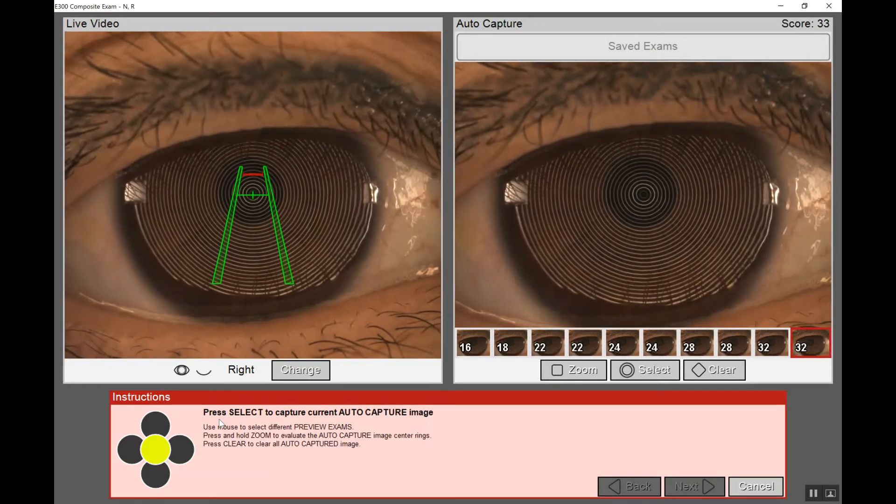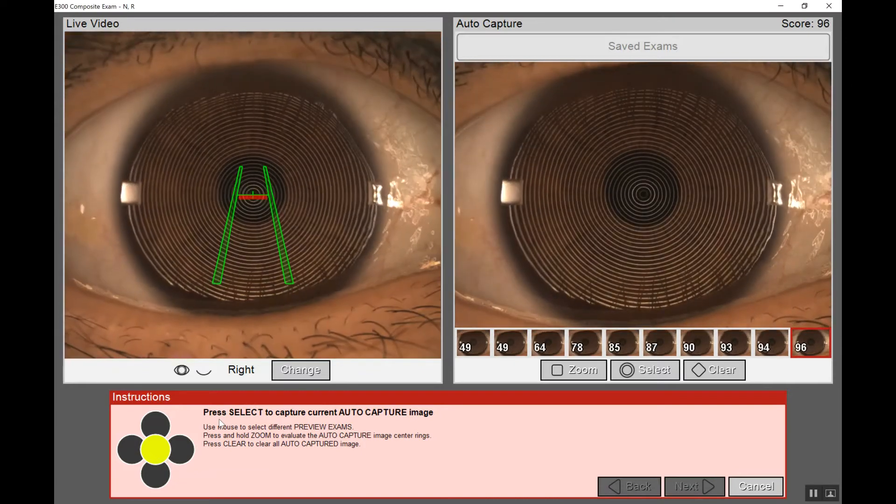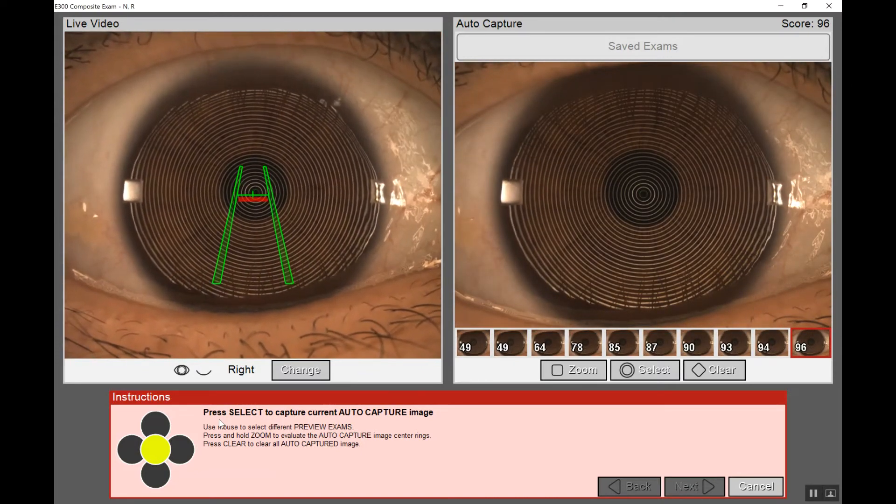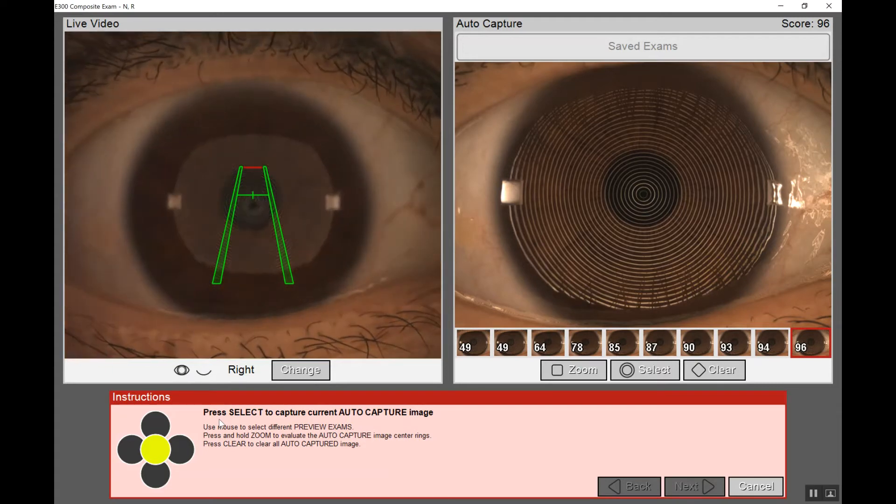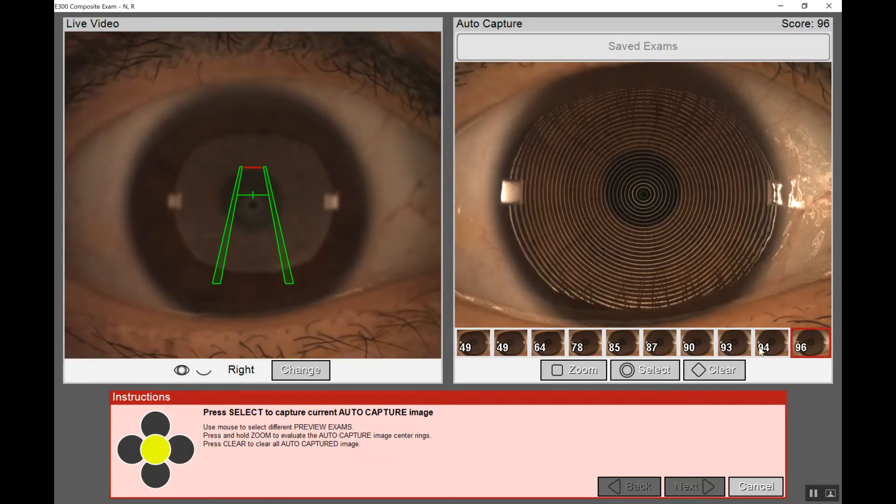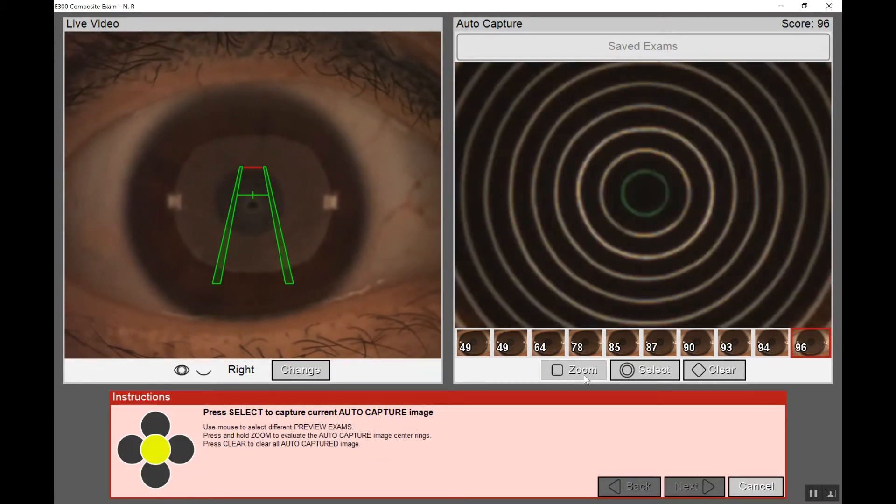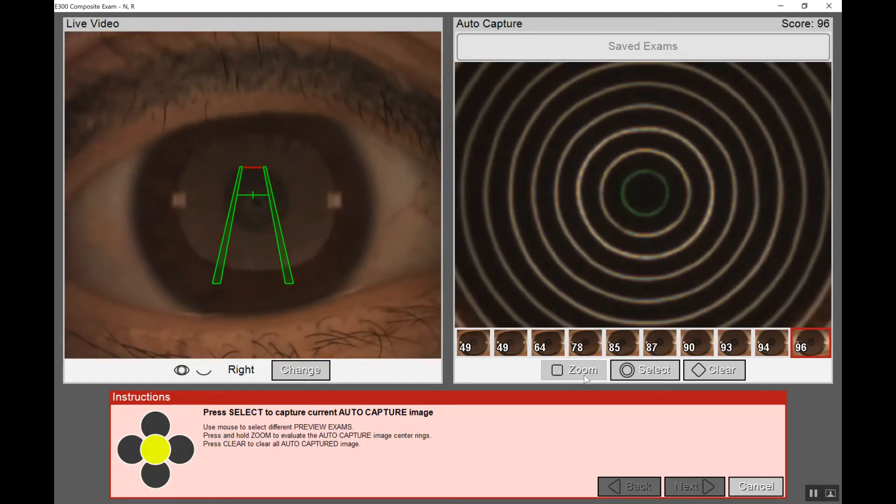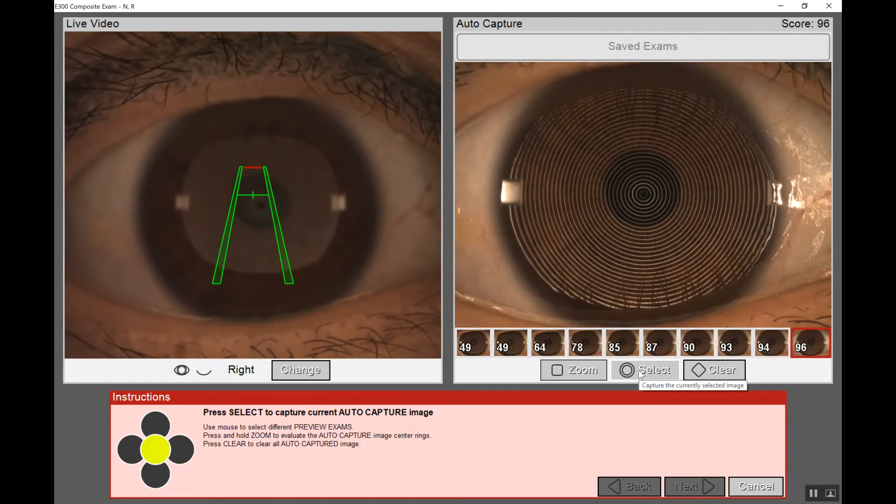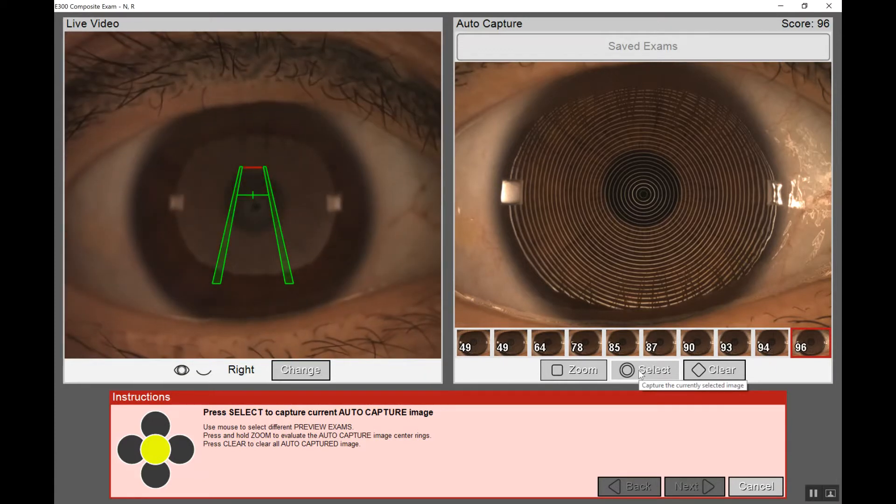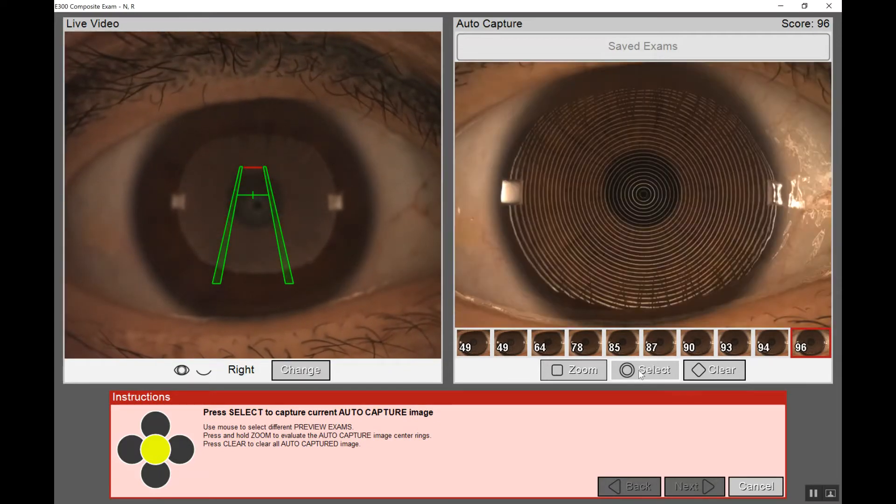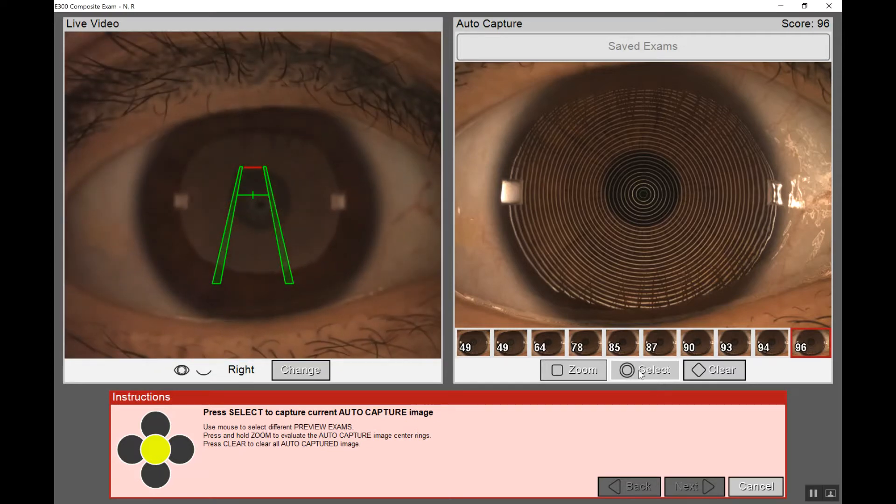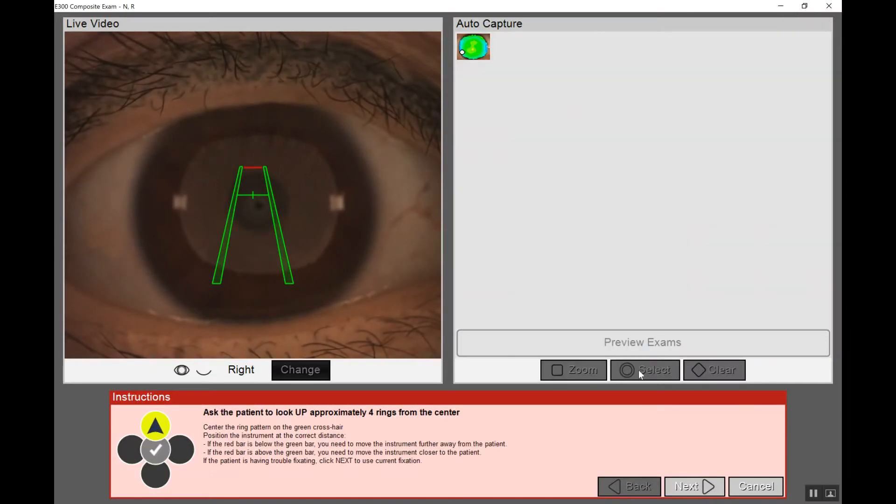Let's start by asking our patient to open up as wide as they can and then we'll move in slowly and steady until we get a 90% or better capture. Here we can see 90, 93, 94, the highest being 96. Make sure that you zoom in, ensure that the rings look parallel and even. If so then you can use the buttons, either the circle button in the center to select it or the square zoom button just to the left. In this case we're happy with the image so we can select the center circle button.